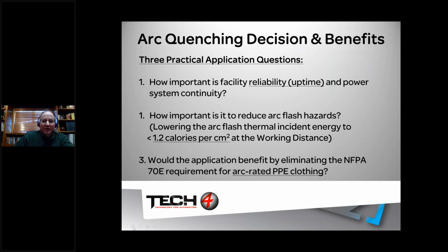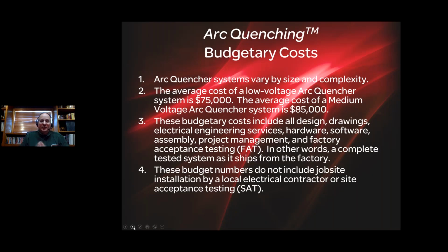The three questions we always ask in arc quenching are: how important is uptime? And what are your goals for reducing arc flash hazards? If the goal is only to reduce it to 8 calories or 4 calories, I want to be clear, we can almost always get there without an arc quencher. But the equipment itself will likely not survive the event. That's when you're focused on safety only. And number three, what's the benefit of eliminating the need for arc rated PPE?